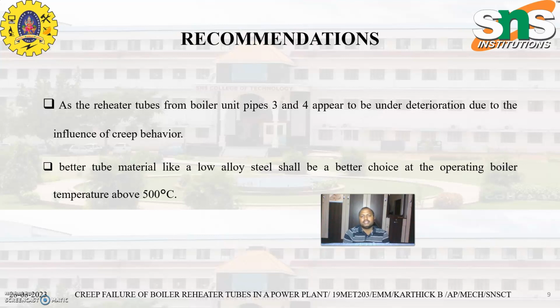Moreover, my recommendation is that cladding can be done in order to avoid rust, and also we can use super alloy steels, which can withstand temperatures of about 1000 degrees Celsius.